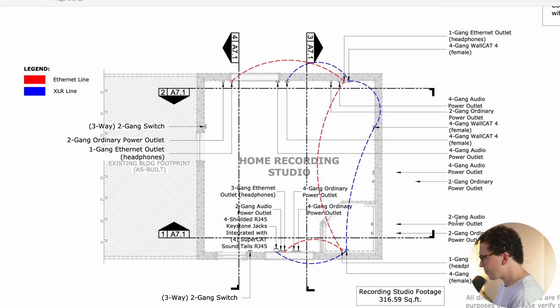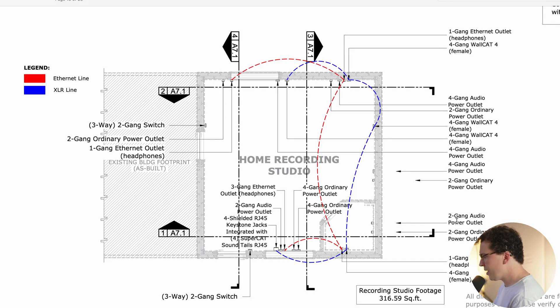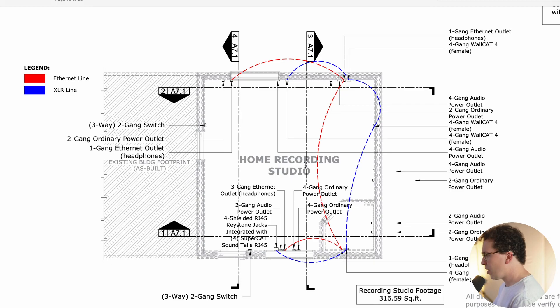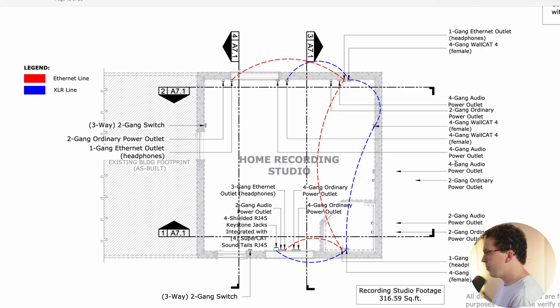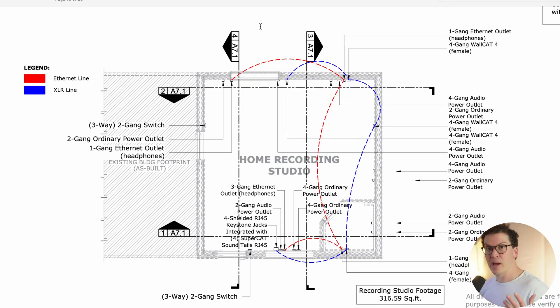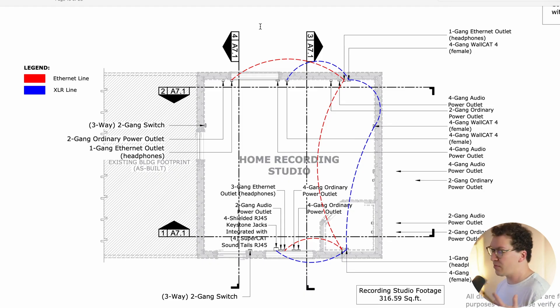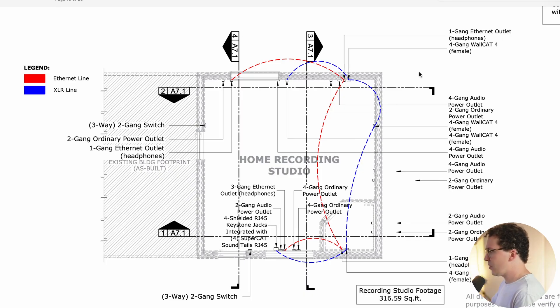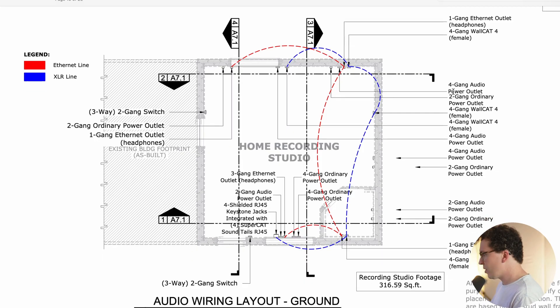We've got the three gang headphone outlet right next to it right here. And then that's all going to be good. They're four gang ordinary power outlet and a four gang ordinary power outlet over there. And then one other thing I'll say is that you generally want to keep your line level voltage at least one foot away from your low level voltage, which ethernet would count as a low voltage line. If they have to cross, it needs to be 90 degrees.